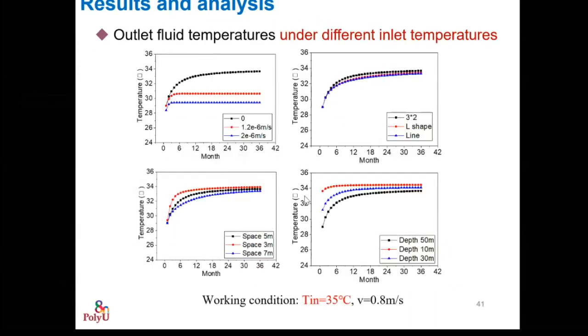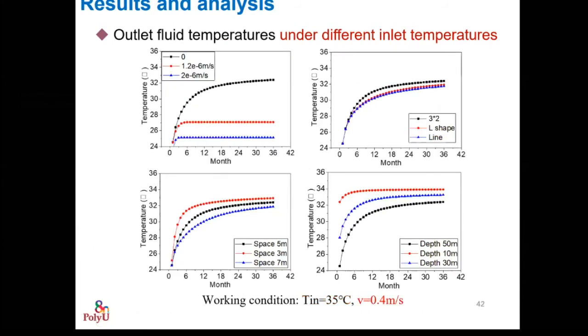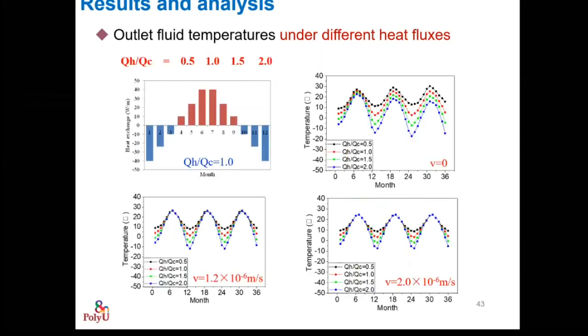So this is our temperature under different inlet temperature. The working condition is inlet temperature 35 degrees Celsius for cooling in summer, with velocity of water inside the pipeline at 0.8 meter per second. We can find the temperature distribution for different layouts, and this is for different depths, different spacing of the system.